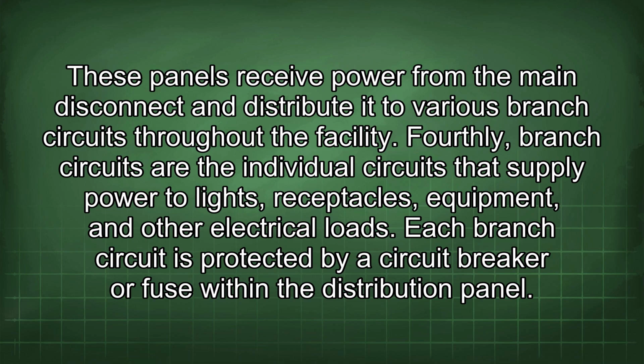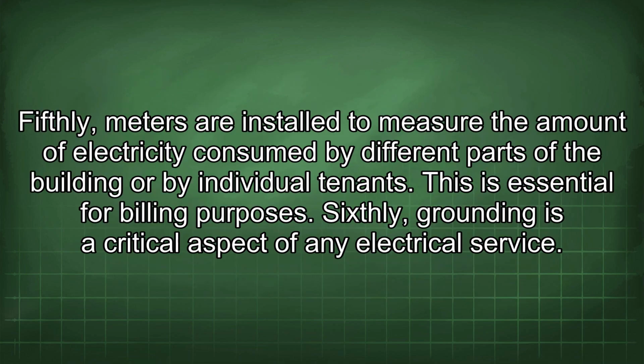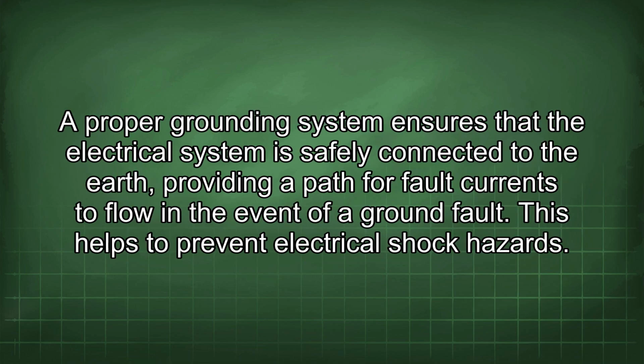Fourthly, branch circuits are the individual circuits that supply power to lights, receptacles, equipment, and other electrical loads. Each branch circuit is protected by a circuit breaker or fuse within the distribution panel. Fifthly, meters are installed to measure the amount of electricity consumed by different parts of the building or by individual tenants. This is essential for billing purposes. Sixthly, grounding is a critical aspect of any electrical service. A proper grounding system ensures that the electrical system is safely connected to the earth, providing a path for fault currents to flow in the event of a ground fault. This helps to prevent electrical shock hazards.